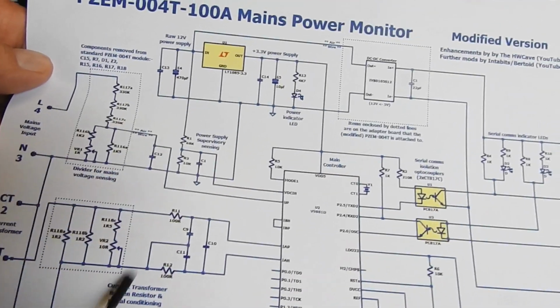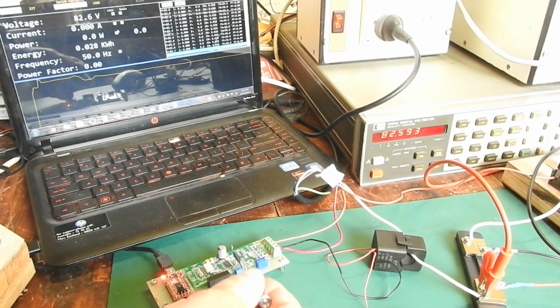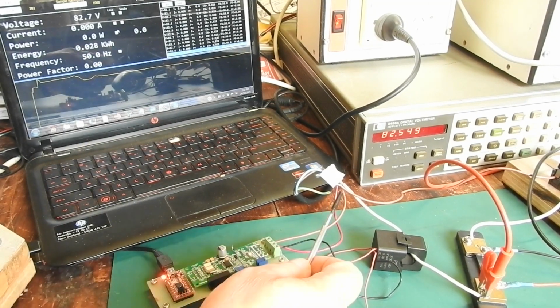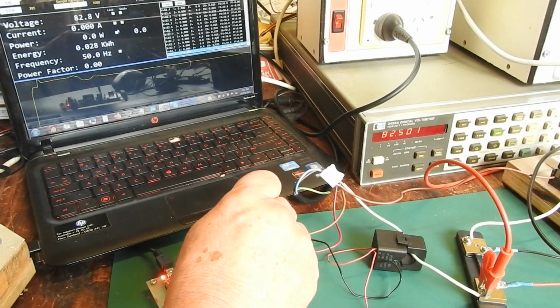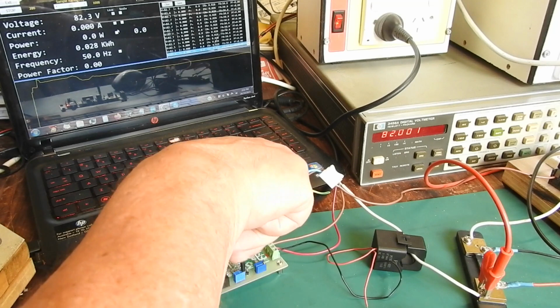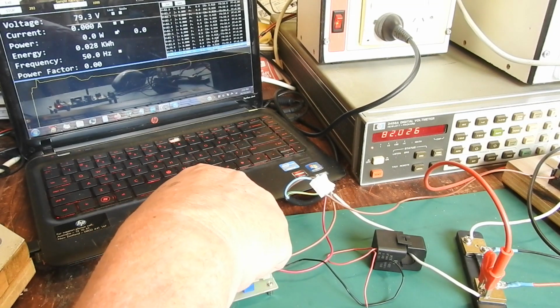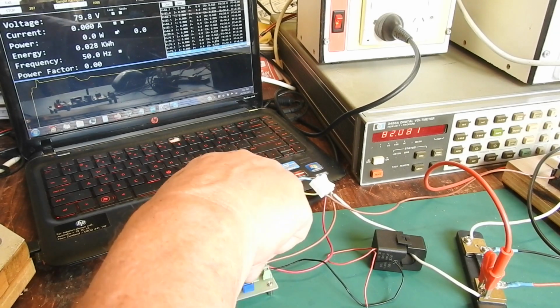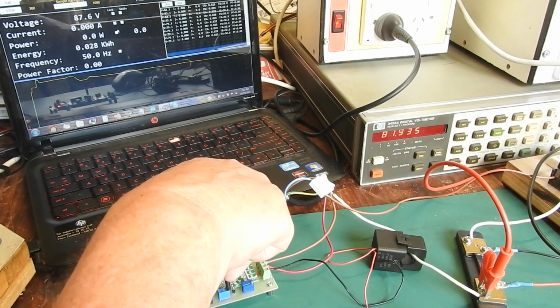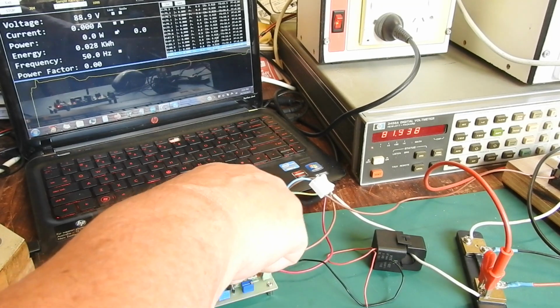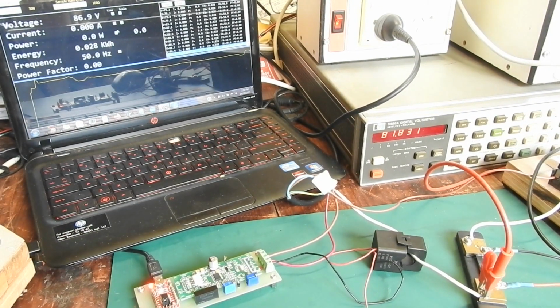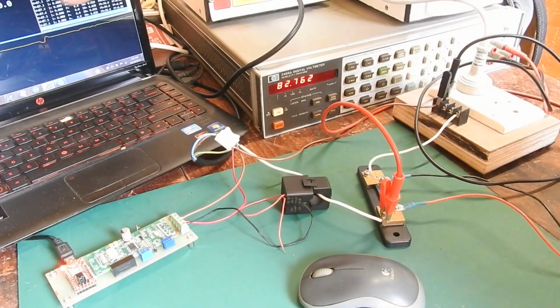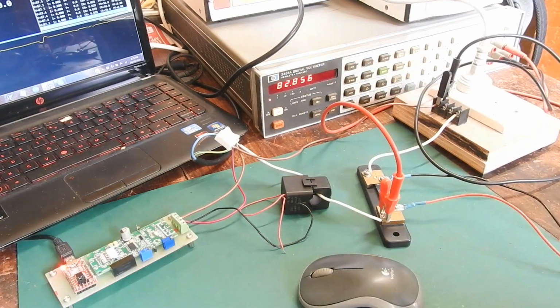Okay, those new parts are on as per this, which I showed just a little while ago, highlighting that these resistors have been updated, and now I can get the voltage to agree pretty easily - 82.5, 82.7, you'll see there's quite a lot of adjustment range. I can spin this well below what that says, 79 versus 82, or spin it well above. Might even be too much range now - yeah, 88 over 81, probably is more too much range. I probably should have just tried to get it to 10%, maybe even only 7.5. Anyway, it's really about minus 11 to plus 18. The current one is about plus or minus 14. And now it's hard to nail down getting that to agree with this, because the mains voltage fluctuates so much.